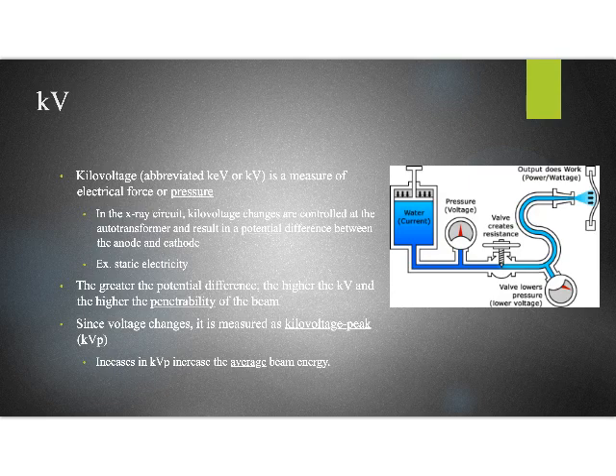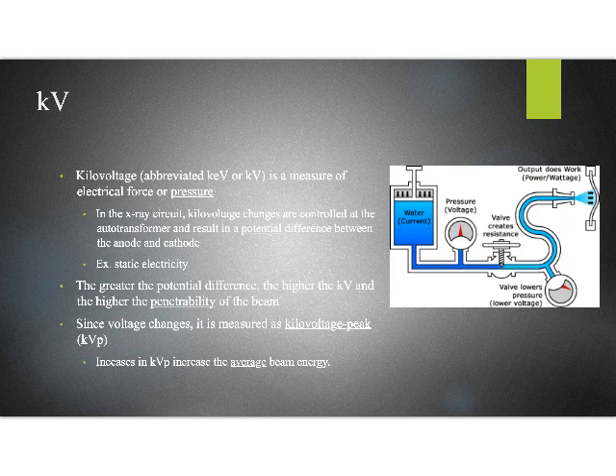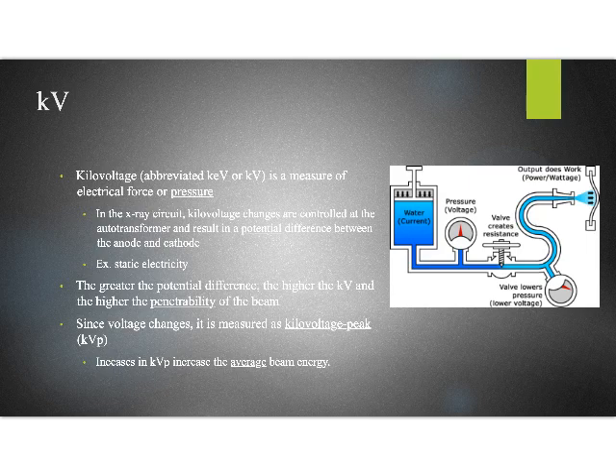That metaphor is very helpful, but we're going to talk about kilovoltage as a measure of electric force or pressure. The way that kilovoltage is controlled within the x-ray circuit is at the auto transformer. We actually change the number of windings that we're accessing at the auto transformer, and this results in different potential differences across the x-ray tube. As we turn up the KVP, we're increasing the potential difference across the x-ray tube and increasing the power that's drawing the electrons across that gap to produce x-rays.